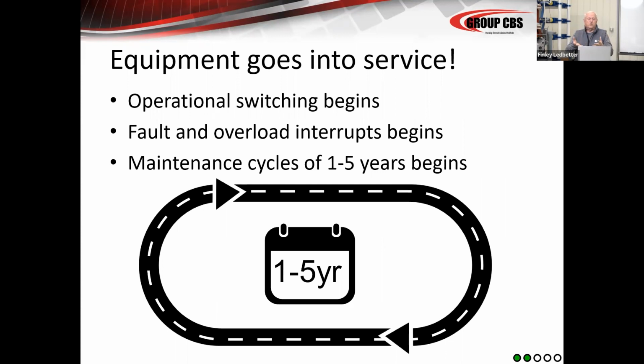Then you've got a 1 to 5 year maintenance period. Please don't go beyond 5 years with that initial maintenance period. But there again, is it 1, 2, 3, 4, 5, 6, 7? What is it? Depends upon your requirements. It depends upon the criticality of the circuit. It depends on the condition of the atmosphere that it's in. Is it in a clean, pressurized room, a long ways from the ocean at sea level? It's kept at ISO. It's distribution gear. It's very seldom opened or closed. Probably 5 years is okay.